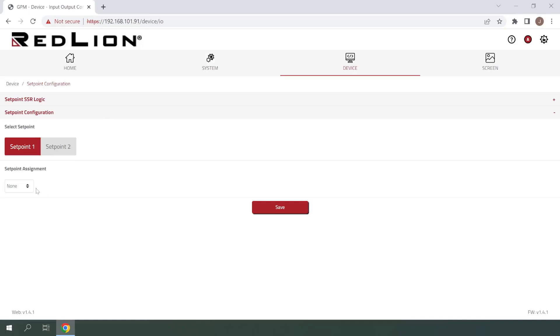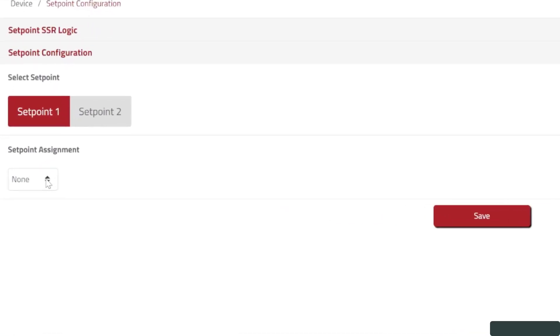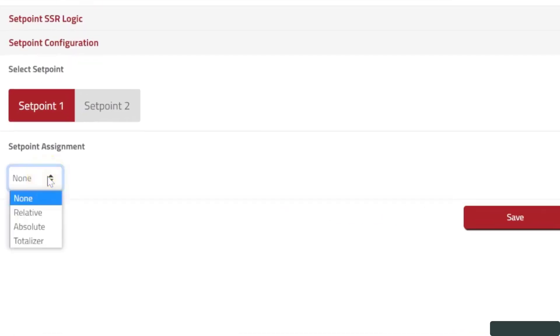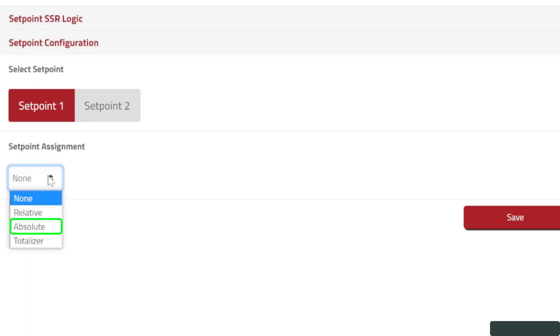Under the Setpoint Assignment section, there is a drop-down menu where we can choose from None, Relative, Absolute, or Totalizer. A relative setpoint triggers from the relative input value, which includes the display offset value, whereas an absolute setpoint triggers from the absolute input value, which does not include the offset.